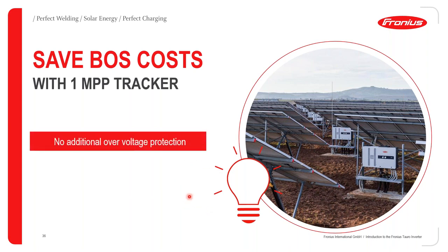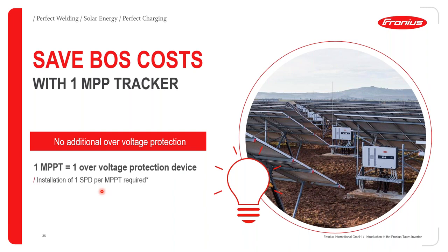Also, another important thing for the Tauro Eco inverters, the 50 and 100 kilowatts: because they have only one MPPT, it means that you require only one set of voltage protection devices. For inverters with more than one MPPT, it would be required in some legislations that you have SPDs to protect each channel of the MPPTs. Therefore, right from the start, when you're choosing your inverter, you have to consider for which application you want to use it. Are you going to use it for a ground mount system or a rooftop system?